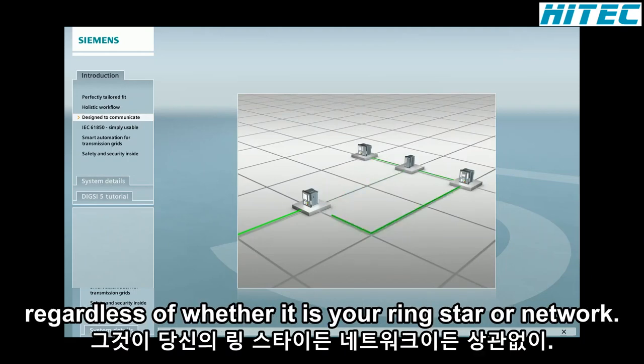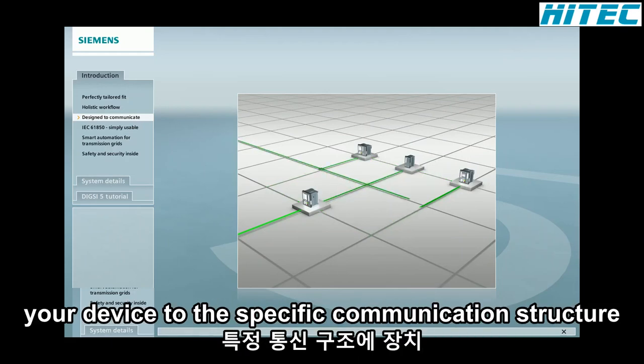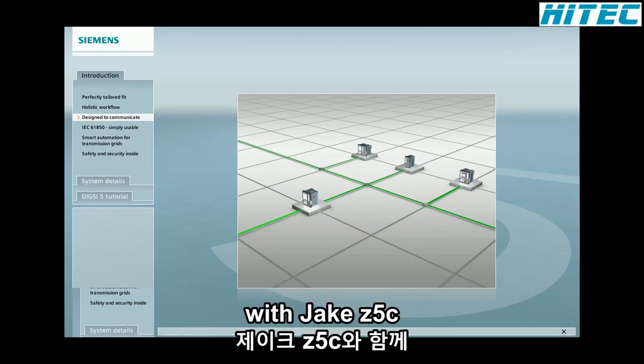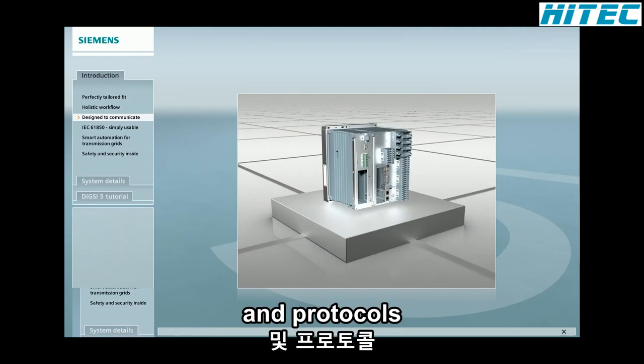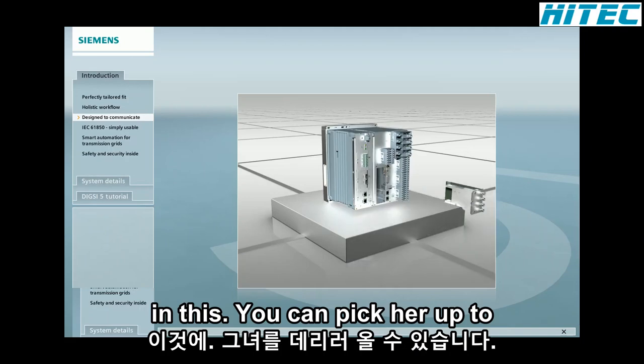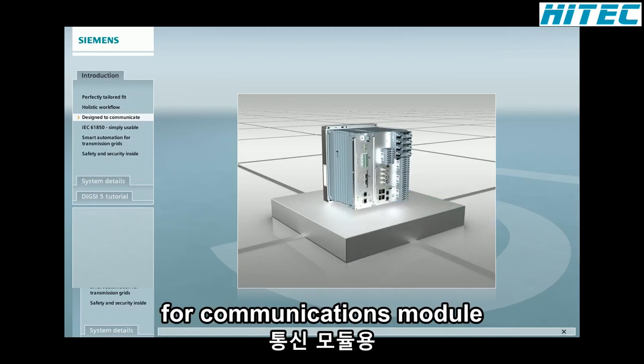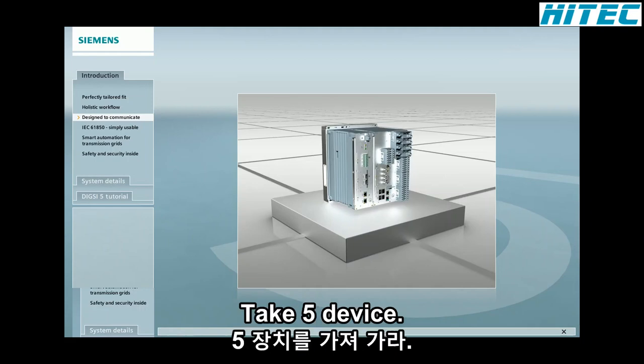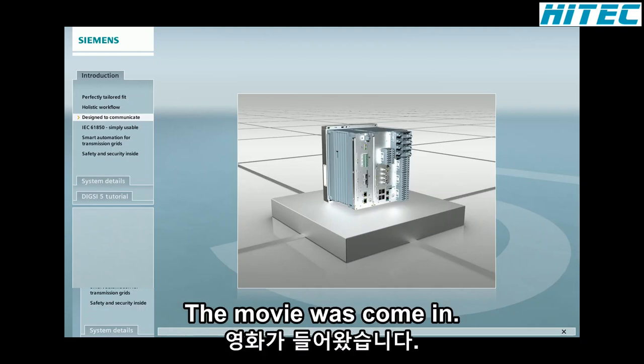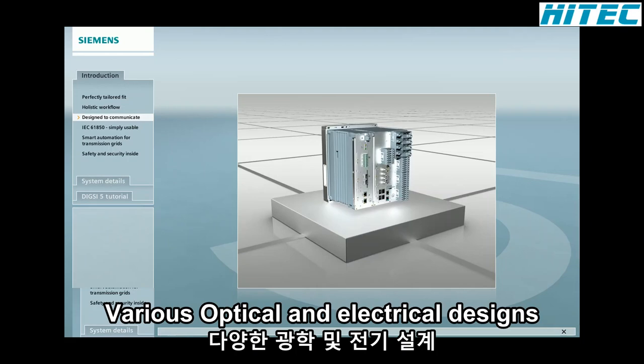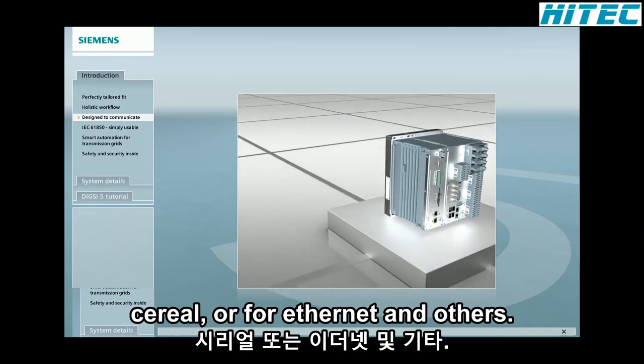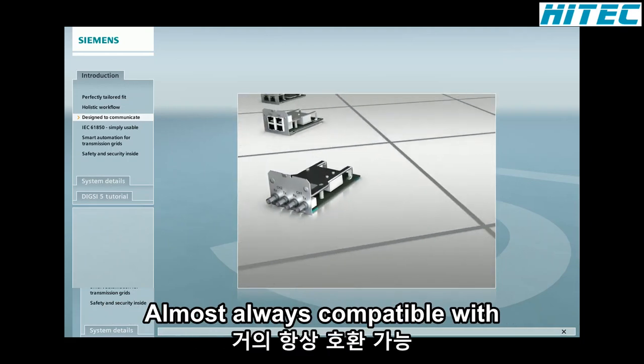Regardless of whether it is a ring, star, or network, you simply adapt your device to the specific communication structure with DIGSI 5. In addition to this flexibility, SIPROTEC 5 offers you scalable redundancy for hardware and protocols. In this way, you can insert up to 4 communications modules in one SIPROTEC 5 device.